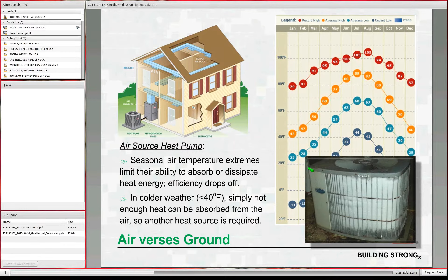There's just not that much heat left in the air, and then you have ice frosting over on the coils. Of course, that's kind of also a defective system. And this is why usually, or actually all the time, air source heat pumps require a backup form of heat that gets used when the temperature drops below that point. Typically electric resistance heat in milder climates where it's not used that much, or where the heating costs are higher, they'd have a separate gas furnace or something like that, gas or oil, to provide the heating that the air source heat pump can't provide.